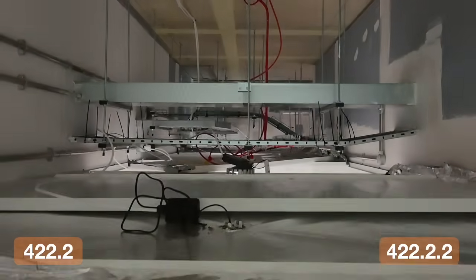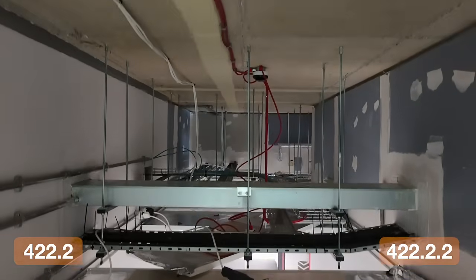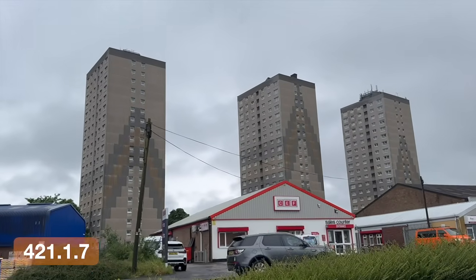This also links into Regulation 422.2 and 422.2.2, which clarify how wiring systems are treated in protected escape routes and fire-resisting enclosures. There has also been a terminology shift in Regulation 421.1.7, where the term high-rise residential building has been replaced with high-risk residential building to better align with building safety legislation.